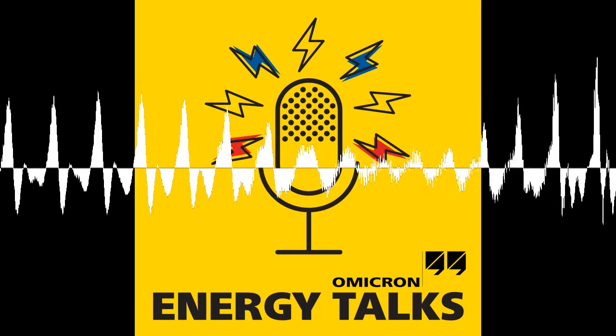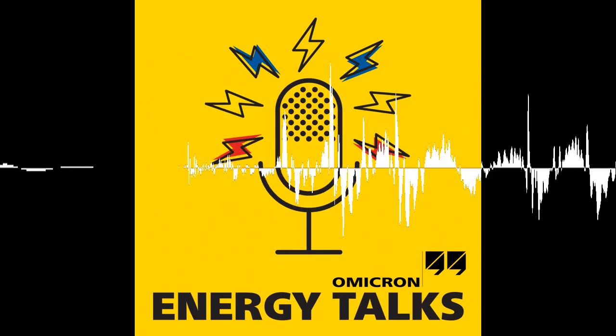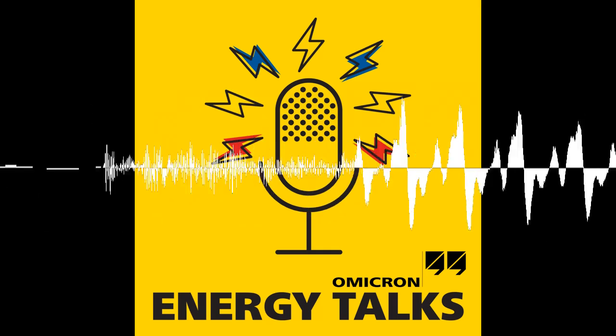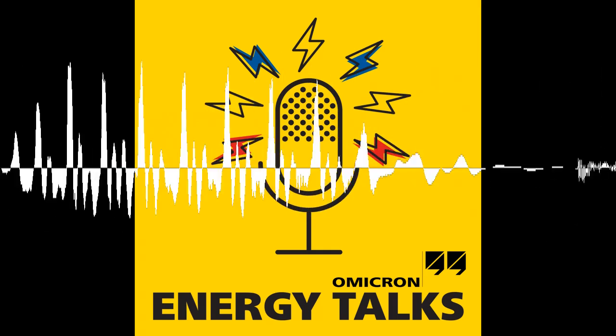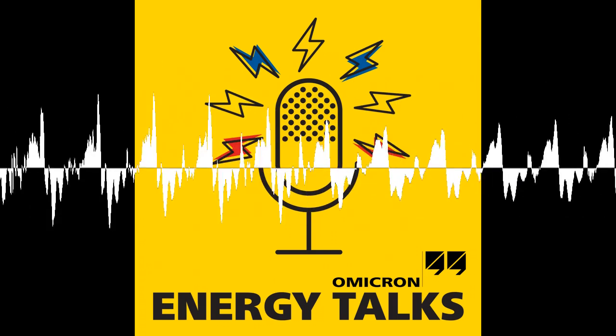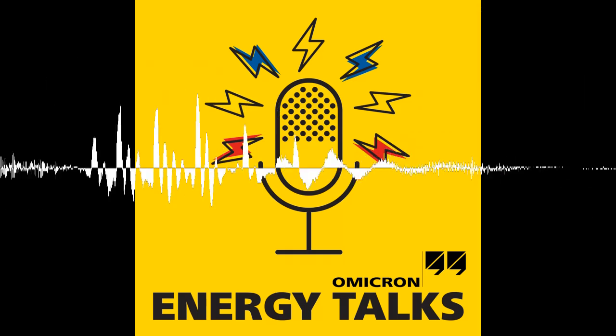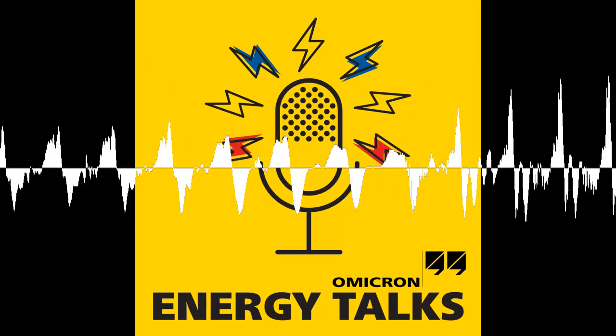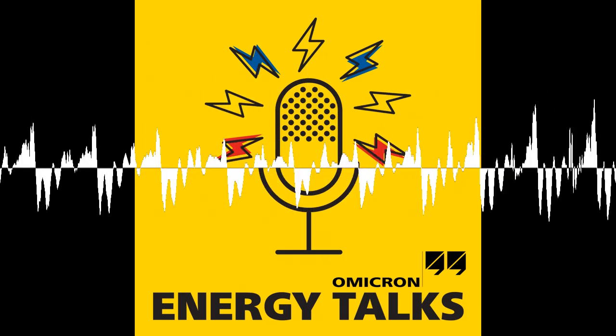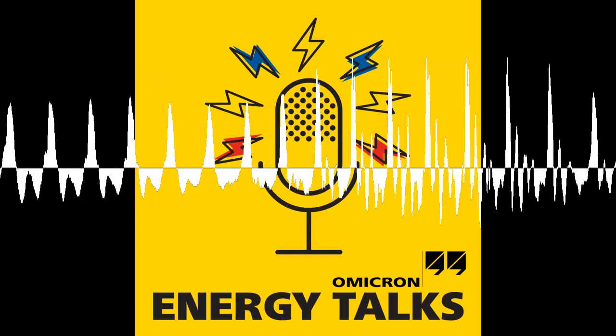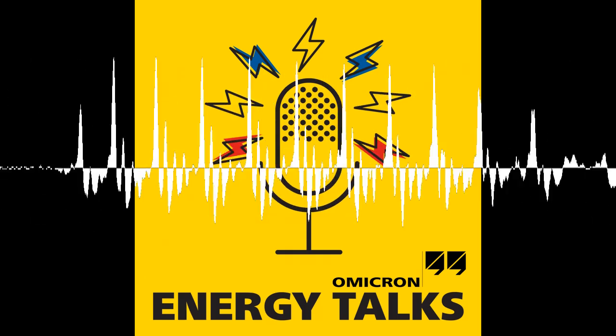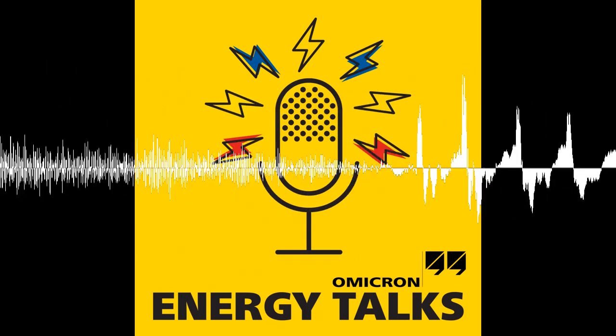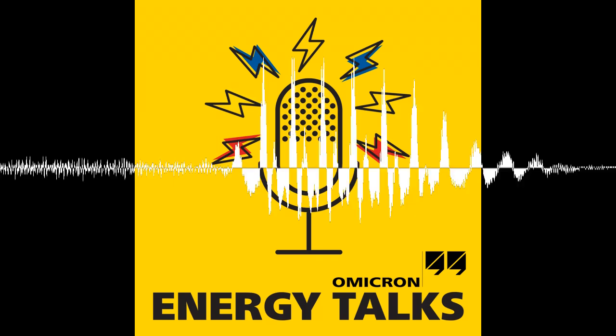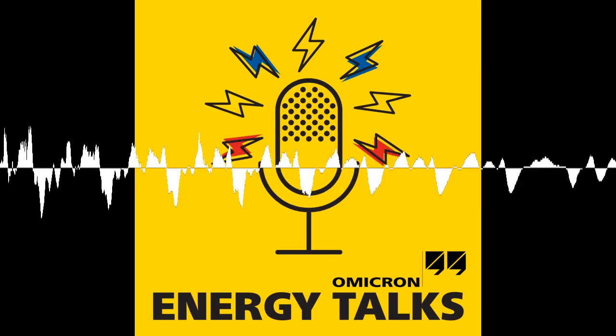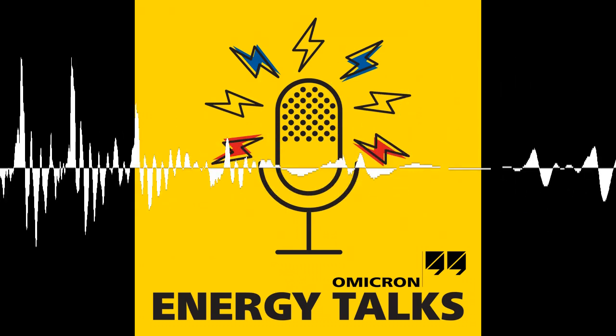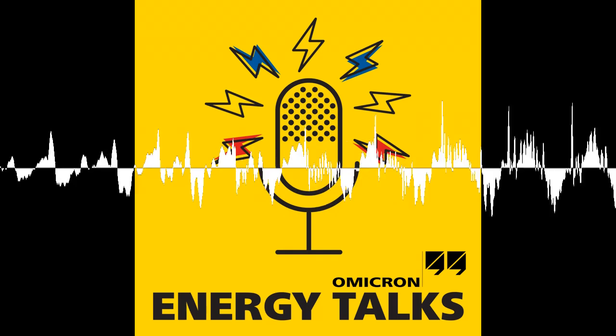In this episode, we dive even deeper into the subject matter and discuss the impact on measurements using the revised EN50522 standard with Josef Schmidbauer, an expert in earthing, also known as grounding testing, and product manager of OMICRON's COMPANO 100. Josef highlights the implications of the EN50522 standard, related measurement procedures, safety considerations, and the recent changes made to enhance safety and reliability. Josef also discusses the importance of touch voltage measurements, interference suppression methods, and the advantages of the newly introduced frequency-selective method for earthing and grounding measurements. Lastly, he explains how modern testing equipment allows for safer and more efficient earthing and grounding testing.